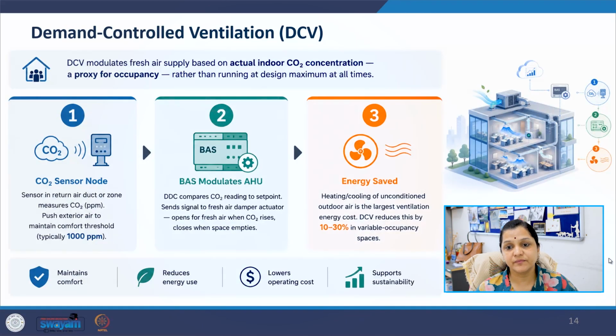In demand controlled ventilation, or DCV, we are able to adjust fresh air supply according to indoor carbon dioxide concentration. Carbon dioxide levels act as indicators of occupancy density. Fresh outdoor air normally contains approximately 400 parts per million of carbon dioxide, while indoor comfort thresholds are commonly around 1000 parts per million. The building automation system compares measured CO2 levels with target values and adjusts dampers accordingly. When occupancy increases, fresh air intake increases. When occupancy decreases, ventilation rate reduces automatically. This strategy reduces the energy required to heat or cool outdoor air. DCV is especially effective in spaces with variable occupancy such as auditoriums, classrooms, conference rooms, and retail environments.